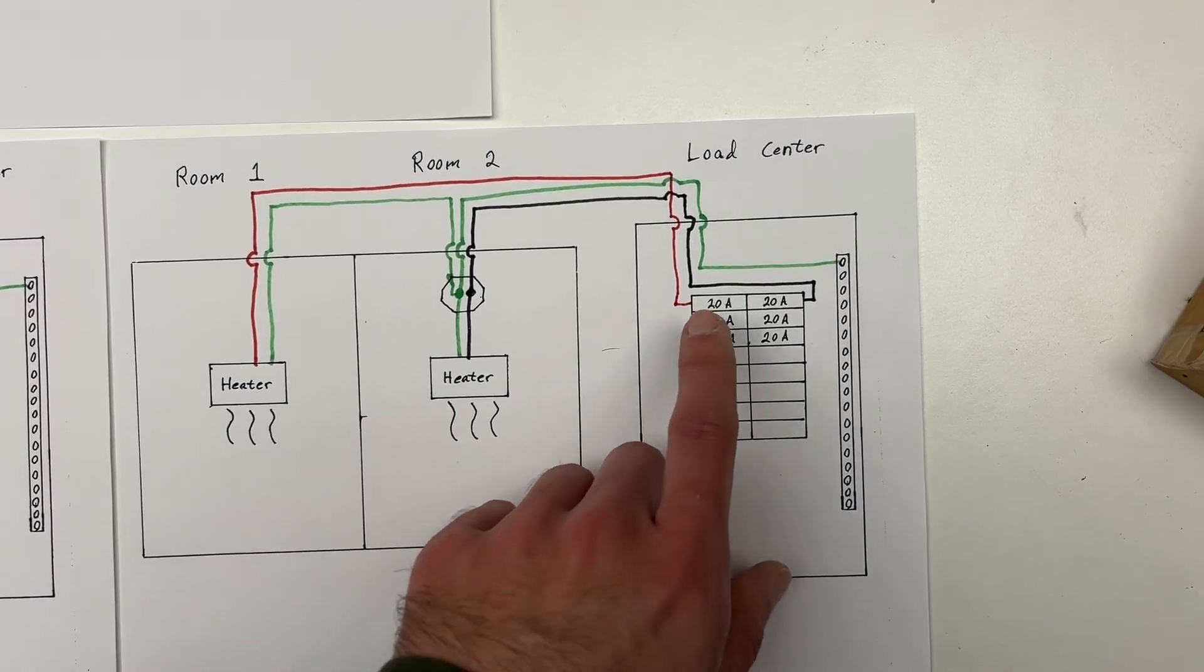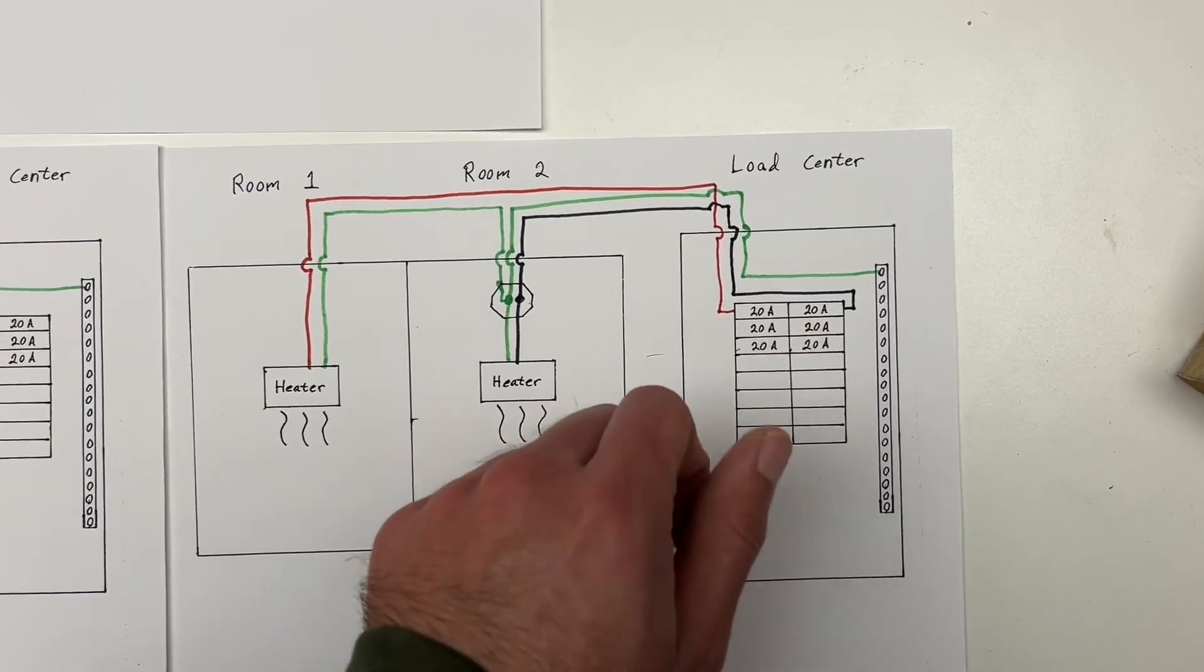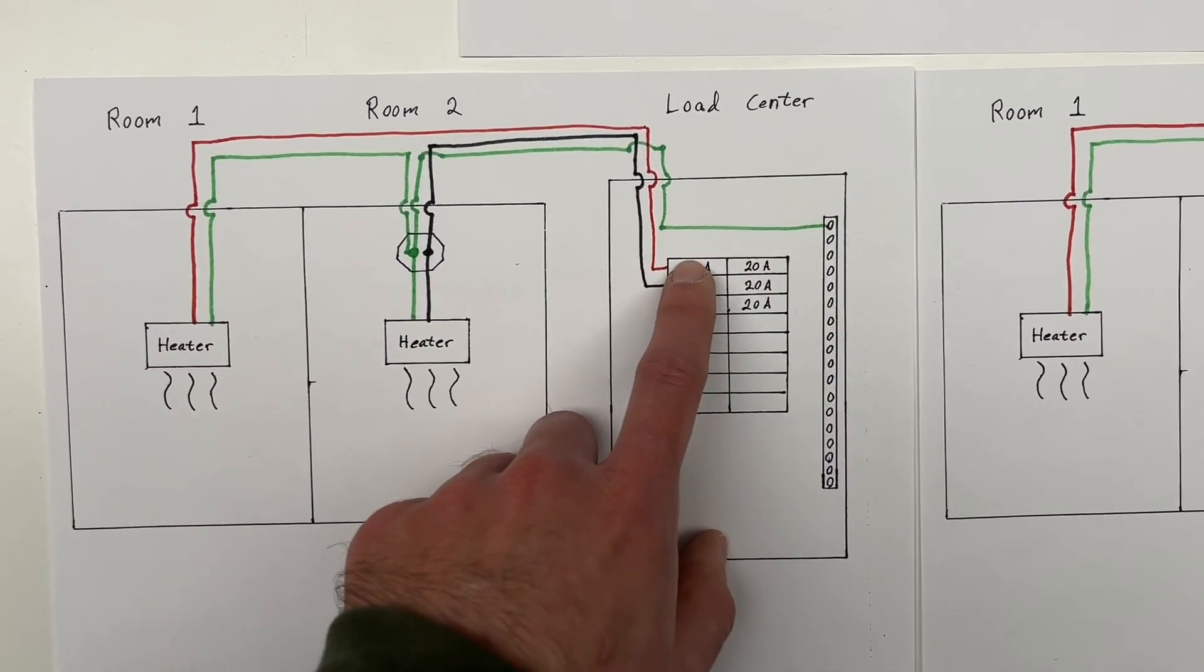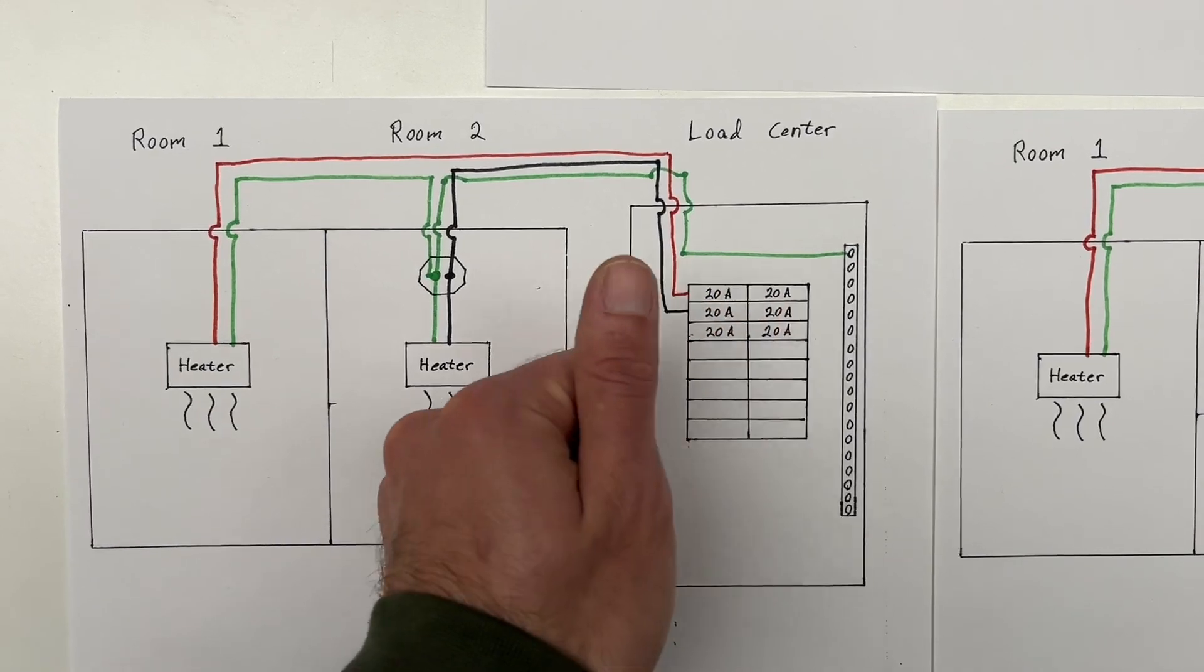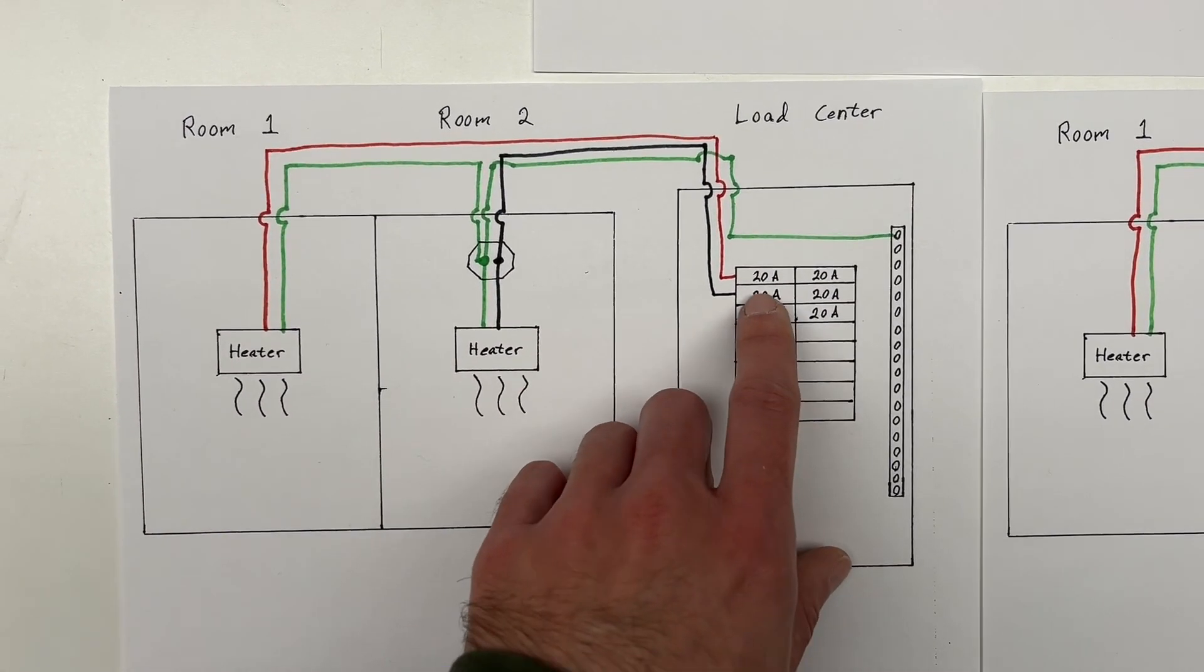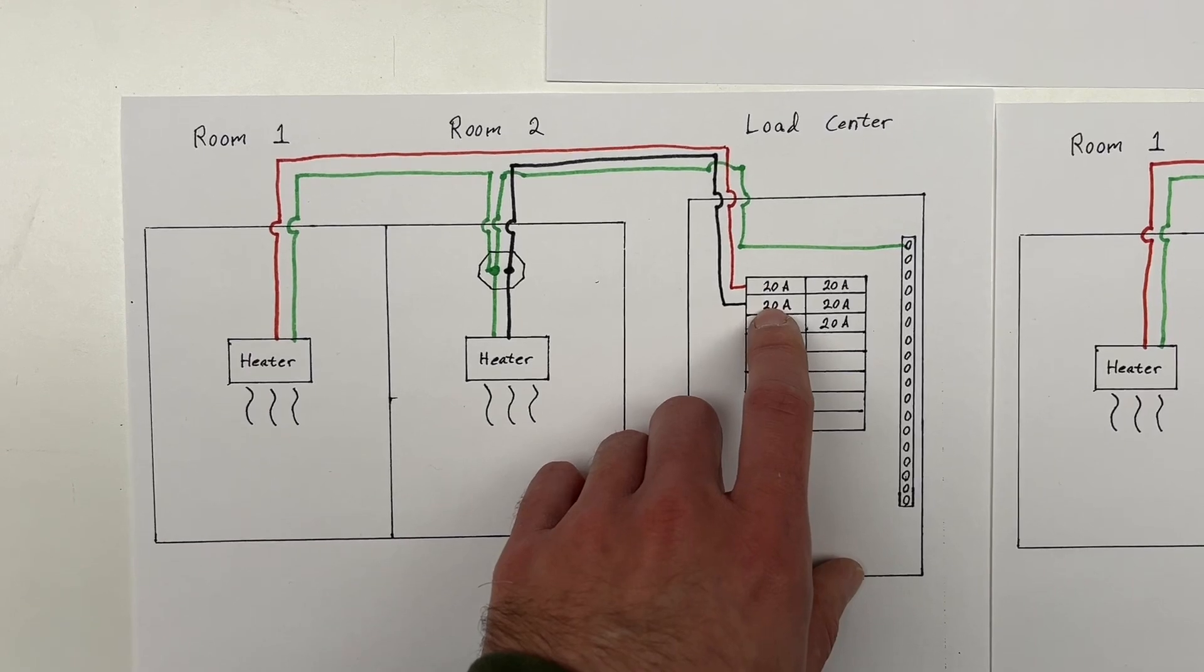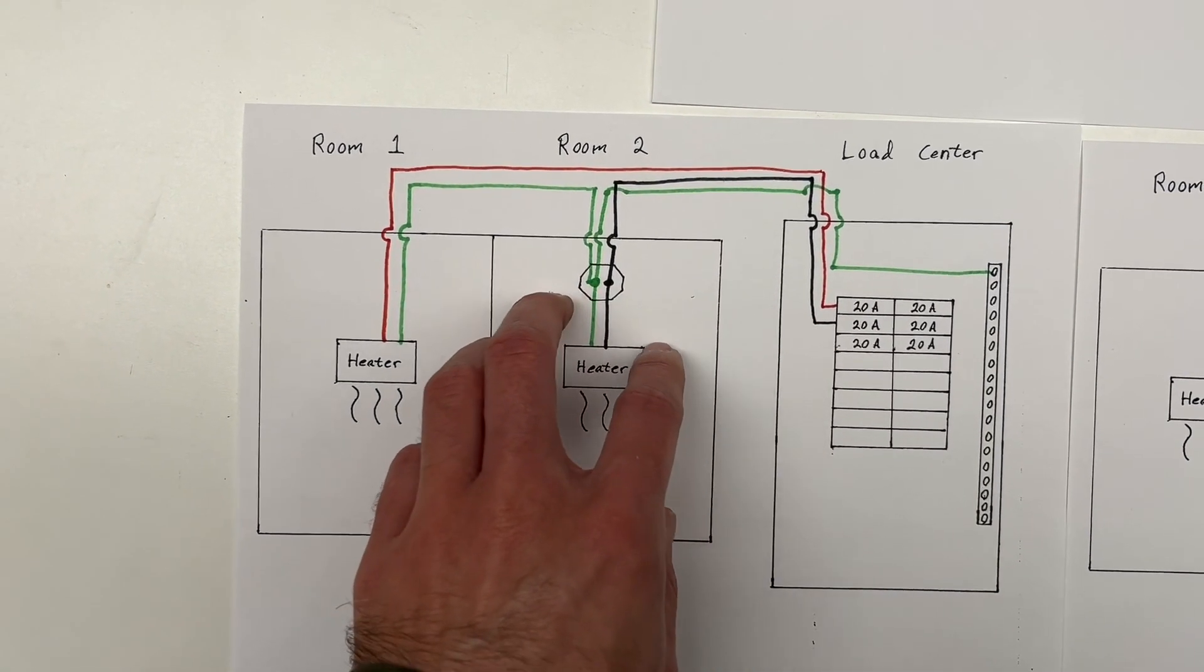One, you cannot switch these off together. In other words, you cannot use a double-pole breaker. That's what you need to do here. These two breakers are drawn as individual breakers, but really there's one lever. These need to be double-pole. The reason for that is that if these were separate, you could turn off the black hot wire. That would de-energize room two, or at least it would appear to de-energize room two.